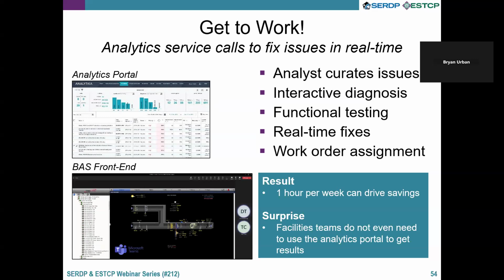The facilities engineer on the other end at the installation would pull up their building automation system front end, look at the same points or air handler, and either confirm or deny the issue. We could even do functional testing in real time, like cycling a valve and watching how temperatures respond. In a lot of cases, we were able to apply fixes in real time, so if a controller wasn't working right or a schedule was incorrect, they could recognize that and fix it on the spot.